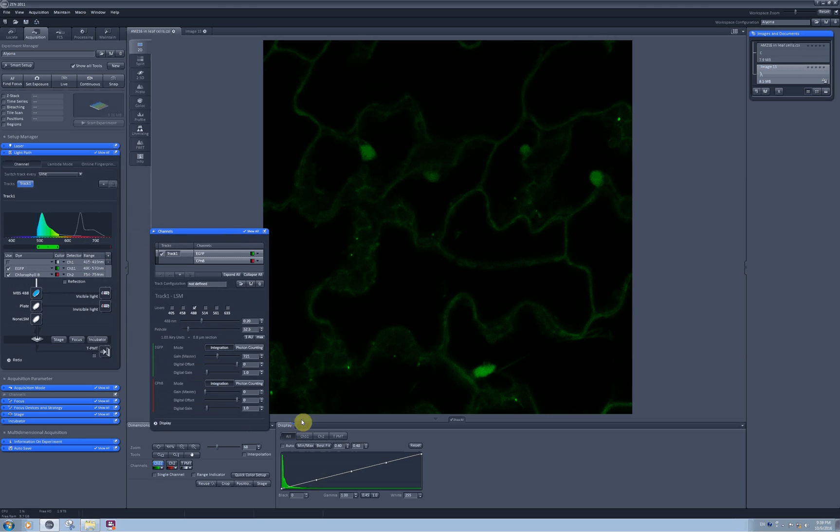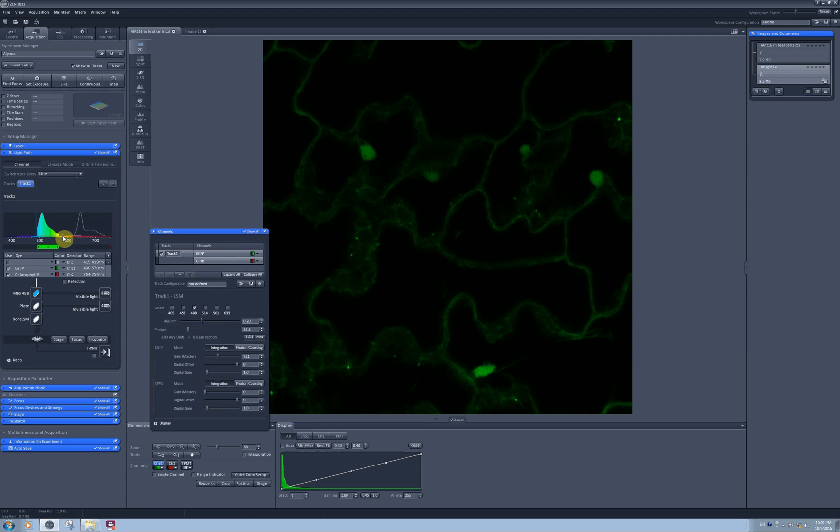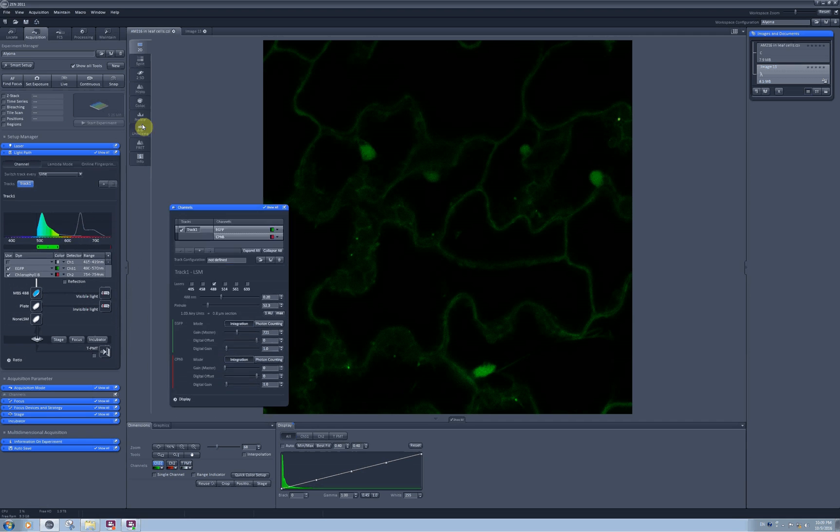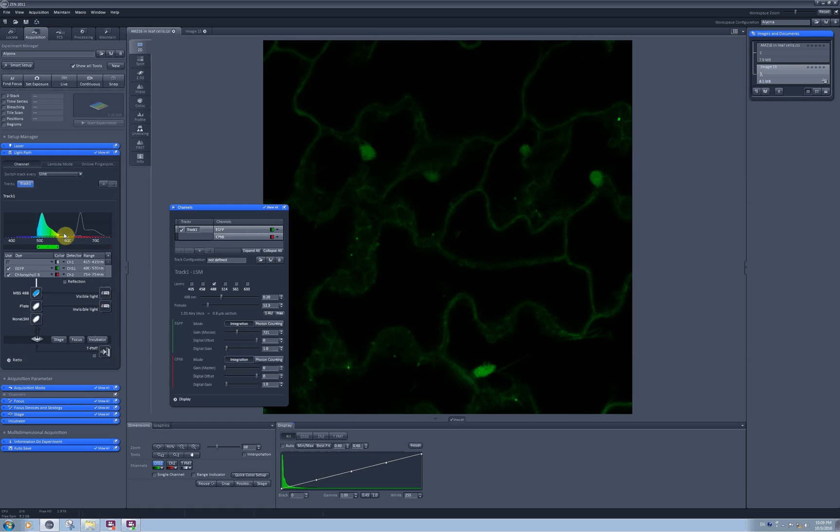For some samples I need to pull the sensitivity of the detector quite high and it increases probability of photons coming from chlorophyll being visible in the GFP channel, which is called crosstalk or bleeding from channel to channel. The unmixing option provides you with the opportunity to subtract photons which most probably came from the chlorophyll from your image in the GFP channel.